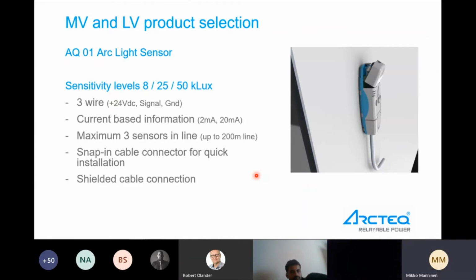It has 3 wires, current-based information, 2 milliamps as a standby and 20 milliamps when active. 3 sensors can be connected in series, in line, up to 200 meters. So the thumb rule is that the last sensor's maximum distance from the device is 200 meters. Snap-in cable connector for quick installation, and shielded cable connection as well.